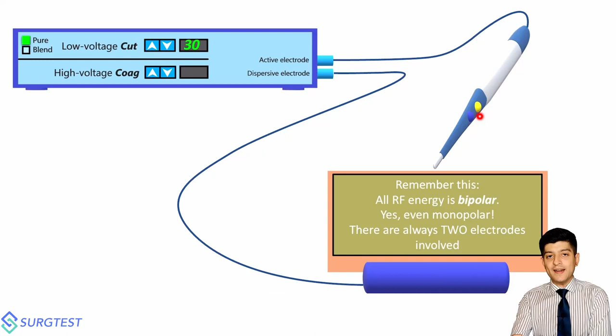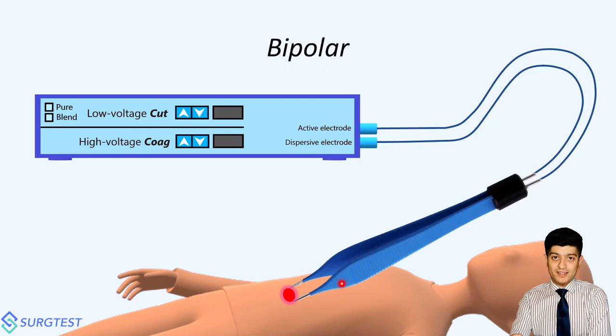I think the definition of monopolar and bipolar should be changed to how many poles are in your hand. So for example, if I'm using a monopolar cautery pencil, that's because only one electrode is within the device which is in my hand. Whereas if I'm using, say, let me go back, a bipolar device, then both electrodes are in my hand at this point in time, right? So that's bipolar for you.